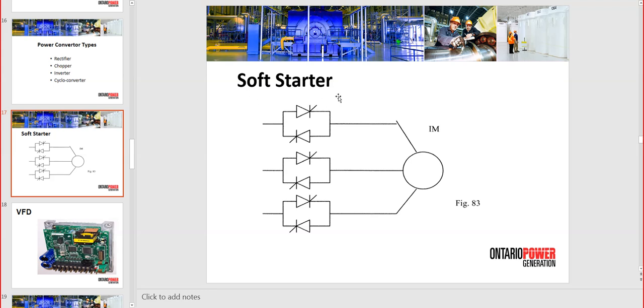Soft starters decrease the inrush. As opposed to having like 9 times, with an off-the-shelf motor the inrush current decreases to only 3-4 times or even less, depending on the application, but it may not be suitable at all for a harsh application because it does not have enough starting torque. So be careful where you are going to use this. A soft starter is not a VFD; it is an electronic implementation of a transformer or autotransformer. So 60 Hertz all the way, variable voltage applied to the motor leads. Now, after the motor starts, another particularity of the soft starter is that you need to take it out of the circuit. You cannot leave the soft starter supplying power to the induction motor, because it is simply going to ruin the motor, because it has very high harmonics.